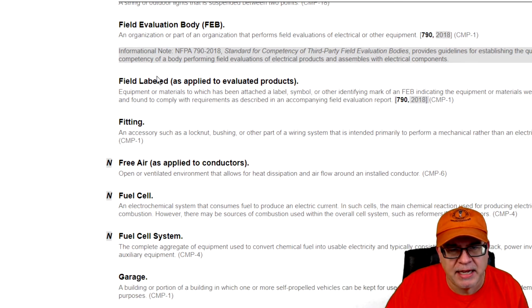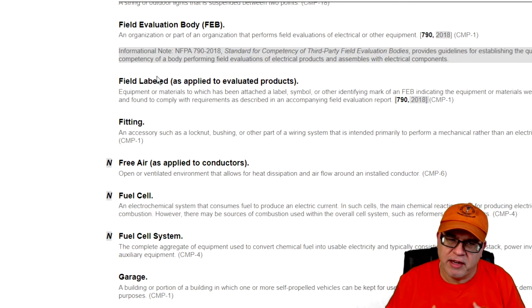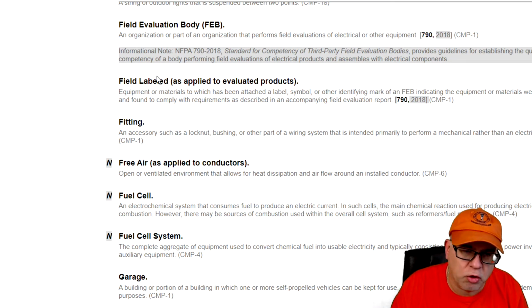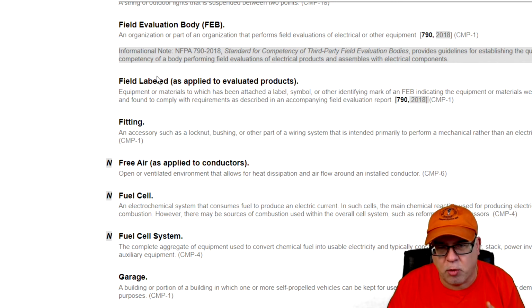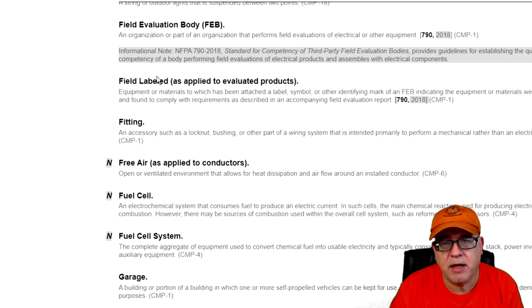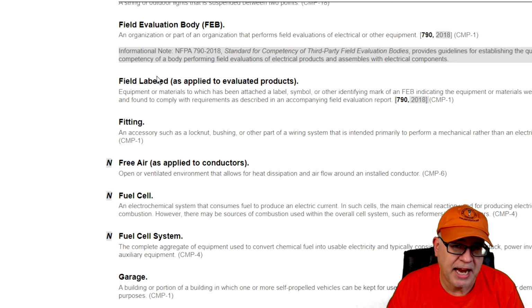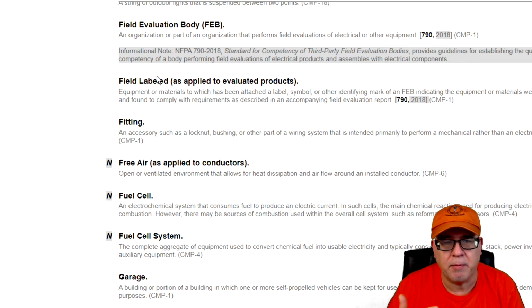Field evaluating body, FEB, that's the organization that's going to come out and do a field evaluation on equipment. If an inspector doesn't like the label or it's a piece of equipment that might be from overseas and it doesn't conform to our normal nationally recognized testing laboratory standards of design, the ANSI UL, then an inspector might say that I need a site evaluation or field evaluation, and then you have various field evaluating bodies that will actually come out and do that evaluation, okay?